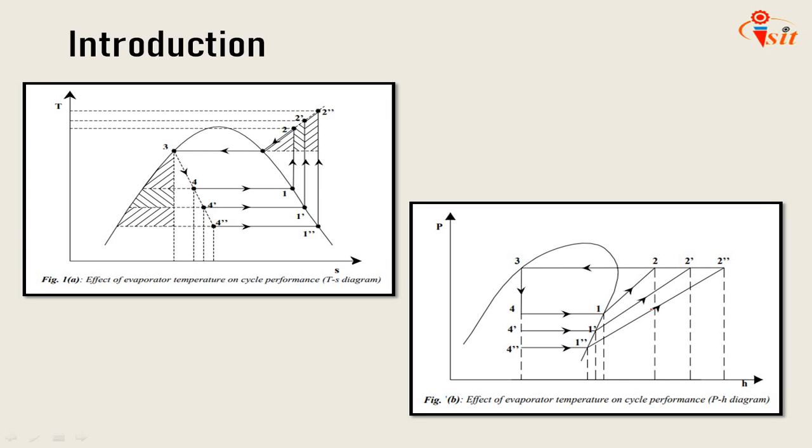On the higher temperature side, the required condensing temperatures can be very high if the refrigeration system is used as the heat pump for heating applications such as process heating, drying, etc. However, as the temperature lift increases, the single stage systems become inefficient and impractical.